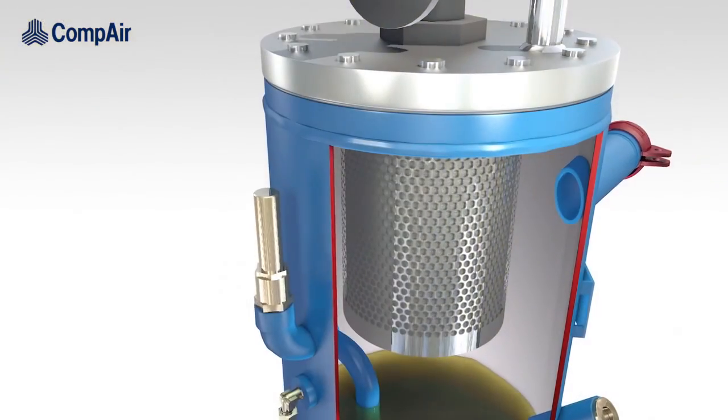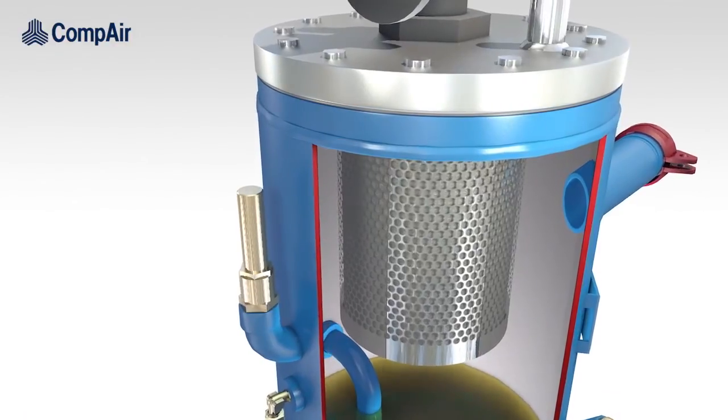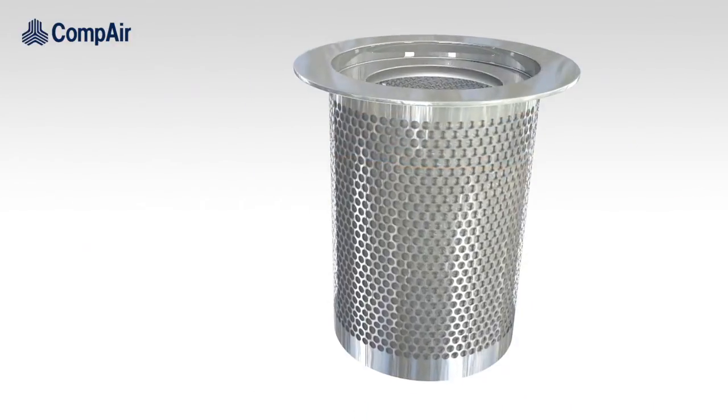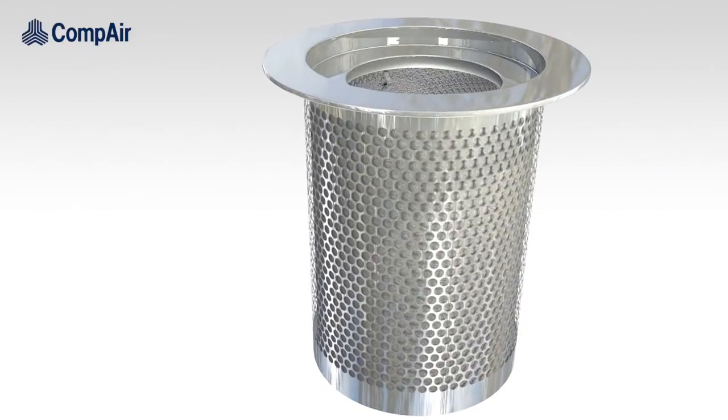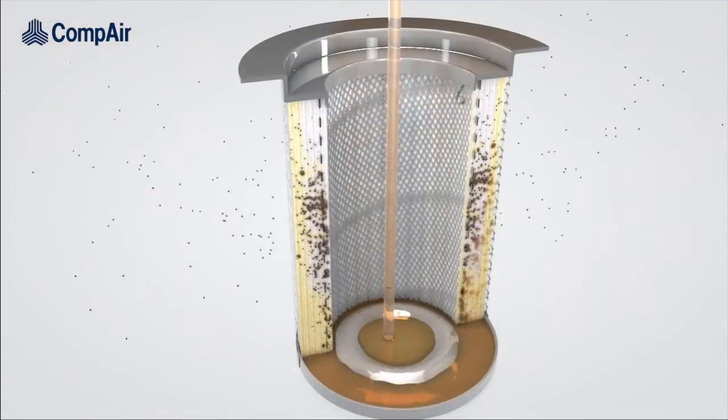In order to achieve a residual oil content of one to three parts per million, a further separation process is necessary. Therefore, the oily air now flows through the air oil separator.